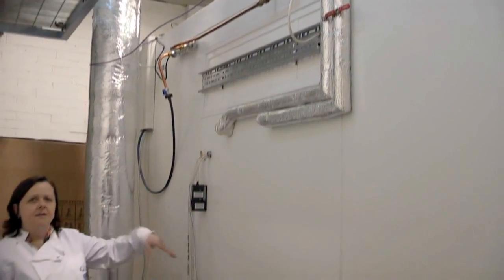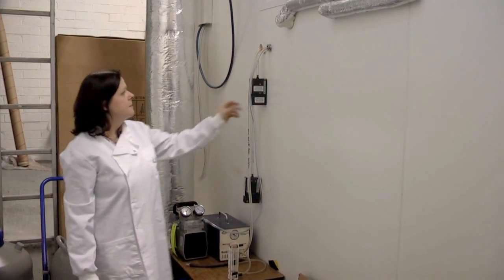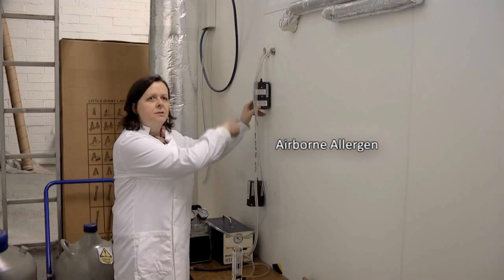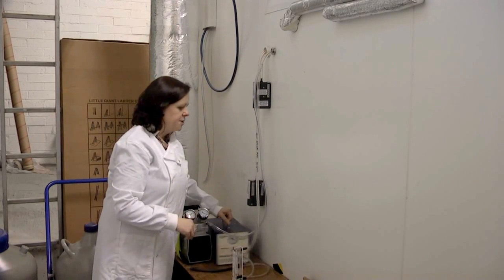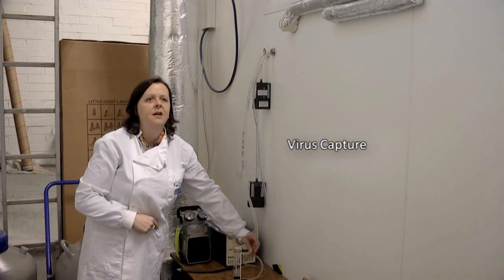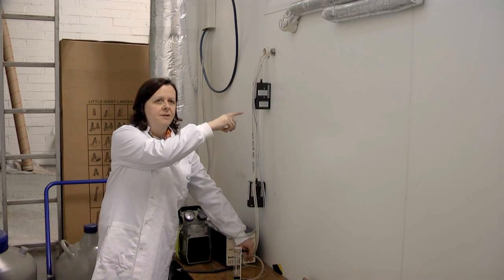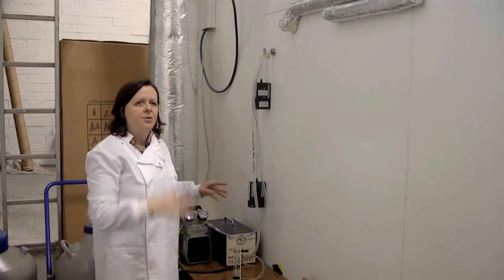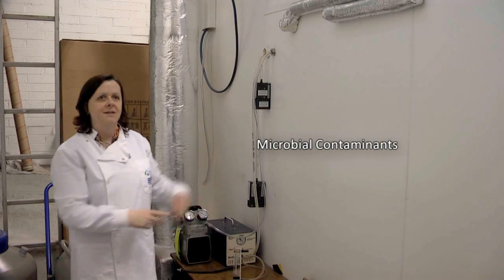On the other side of the chamber there are two additional sample ports used for air sampling. These two sample pumps are used for measuring allergen, trapping them onto glass fibre filters for airborne allergen analysis. This pump here is used for sampling liquids, capturing viruses that are airborne into a liquid collection chamber inside the room. And this sample pump captures microorganisms such as bacteria, viruses and fungi onto petri plates.